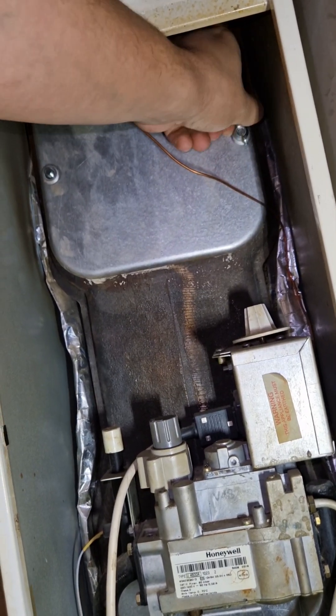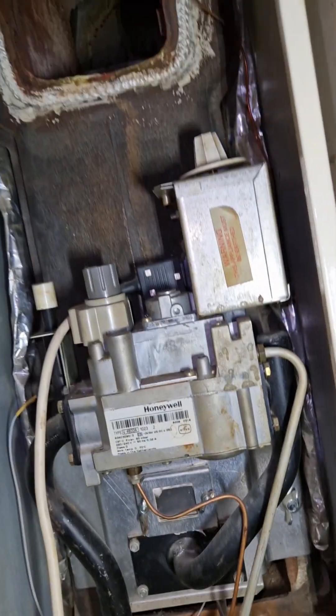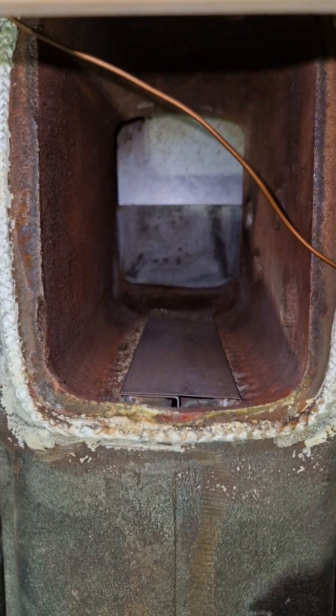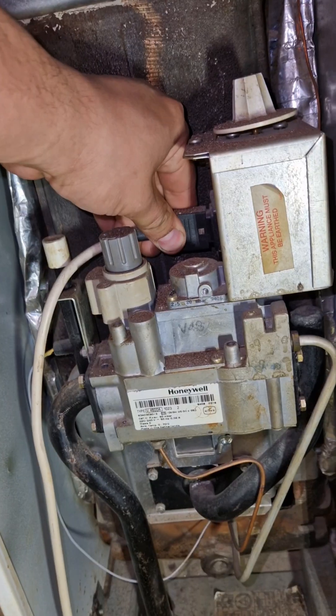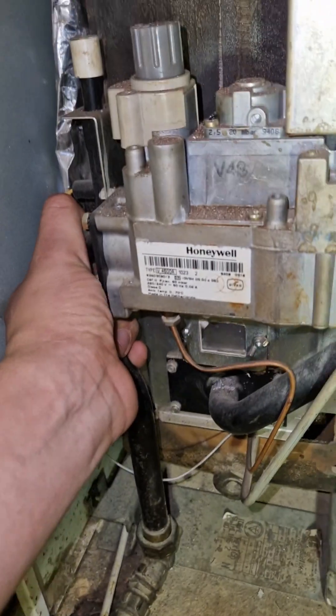Use gloves, people! All that dust is now gone from the back. We shut off the gas, which is here, and we're going to cap it. With the gas isolated, we can undo the nut for the gas pipe, followed by the two butterfly nuts that are holding the burner in. We then just jiggle it around and pull it forward to release the burner.